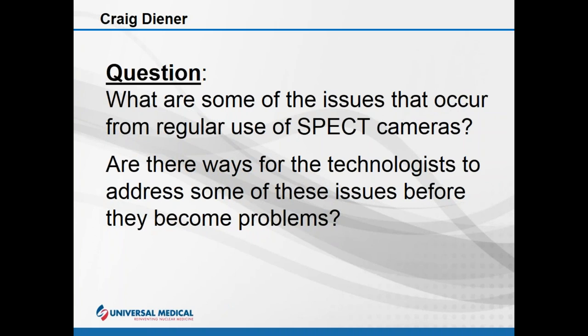So the scanning room should always be kept in an air-conditioned environment between 60 and 80 degrees. Airflow is important in keeping your camera cool. So my suggestion is to do a walkthrough during your daily QA process and make sure the fans are working properly, filters are cleaned, and above all, make sure your UPS is functioning correctly. Just some basic housekeeping and regular PMs will go a long way in keeping your camera running for many years.